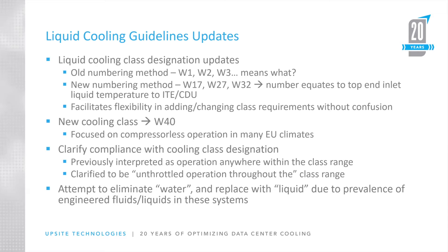We also added an additional cooling class — W40. Quite frankly, the W40 addition is what prompted this whole thing, because we were debating whether to call it W3.5 or W3.8. The water cooling classes are likely to change more over the coming years as technology evolves than the air-cooled classes. By putting the temperature designation at the back end, it becomes much easier to add, subtract, or change a cooling class as needed.